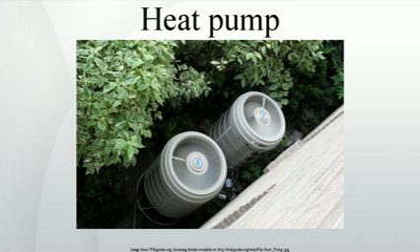In heating mode, the outdoor coil is an evaporator, while the indoor is a condenser. The refrigerant flowing from the evaporator, the outdoor coil, carries the thermal energy from outside air, or soil, indoors, after the fluid's temperature has been augmented by compressing it. The indoor coil then transfers thermal energy, including energy from the compression, to the indoor air, which is then moved around the inside of the building by an air handler.